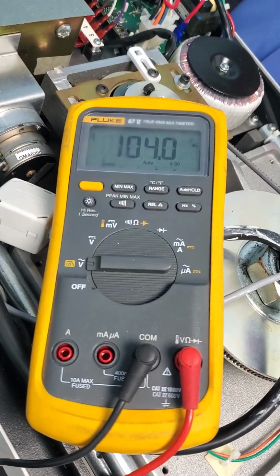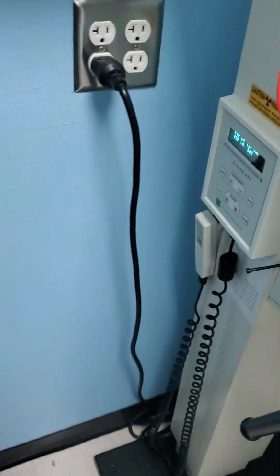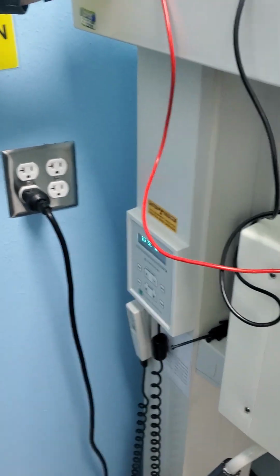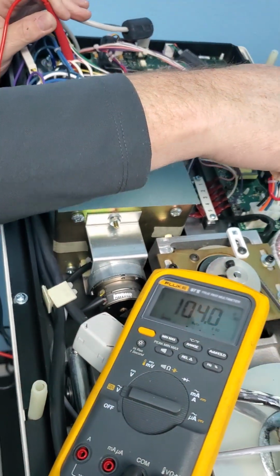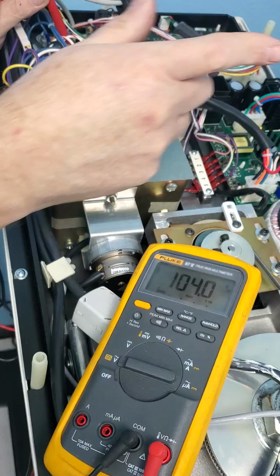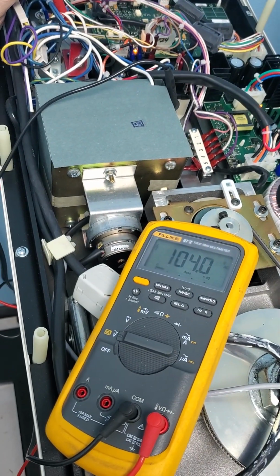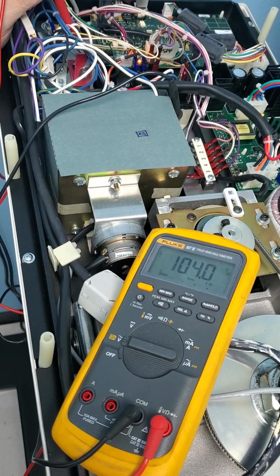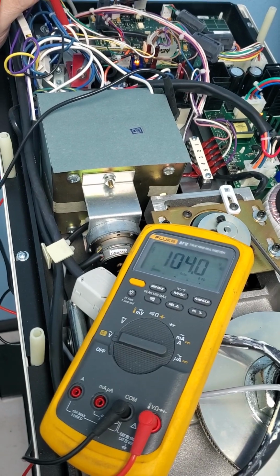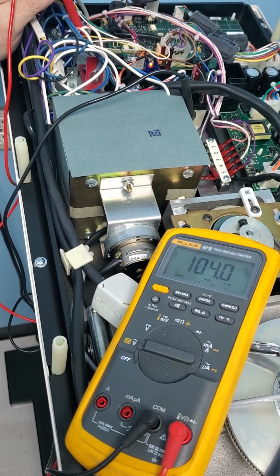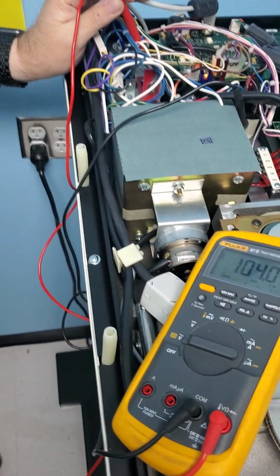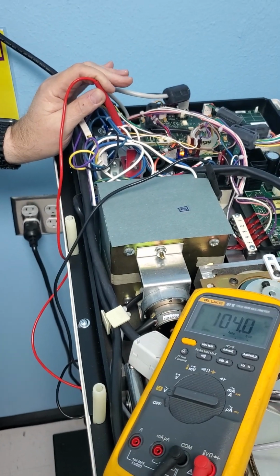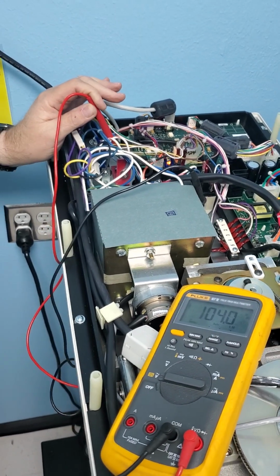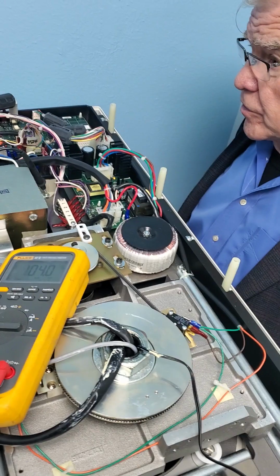What I've encountered when the KVP numbers are this far off is that this power supply board right here is starting to fail, and that may be what we're running into here. I'm going to run the cal twice. We may come back and it may be way off again. I don't know. If it is, that means the power supply board has to be replaced. Are all parts still available for this machine? As far as I know, yes.